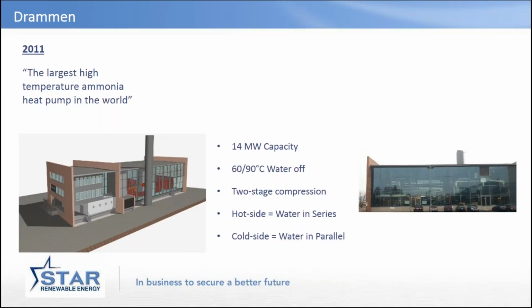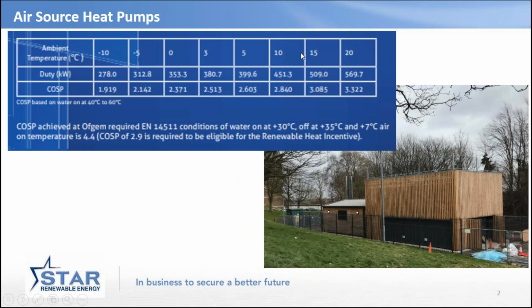What we're doing from the river source heat pump really stems from work we did back in 2010 in Norway. We delivered 90 degrees with an efficiency of 3. So that's from a fjord, delivering heat at 90 degrees to district heating. And just to put that in context, I'm going to jump back to the previous screen. This is for an air source heat pump doing 60 degrees using an HFC, a hydrofluorocarbon, cousin of CFCs. It's got the efficiency of something round about a 15 degree air temperature day, delivering heat at only 60 degrees.